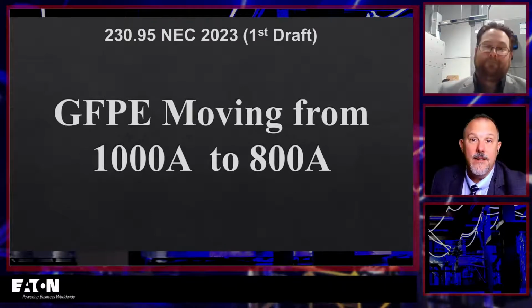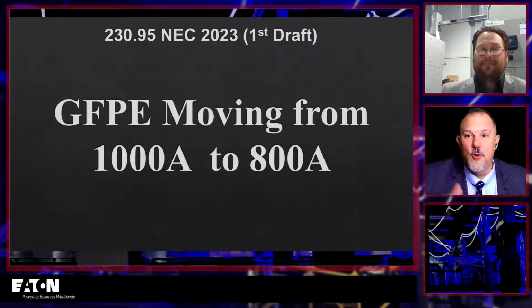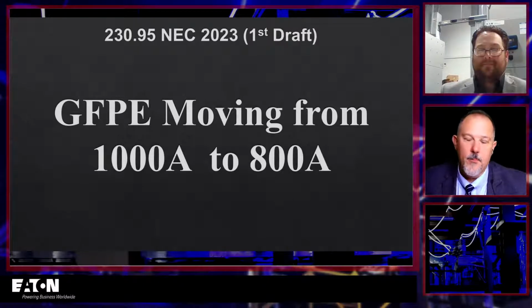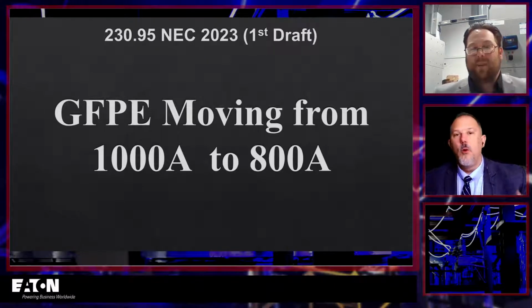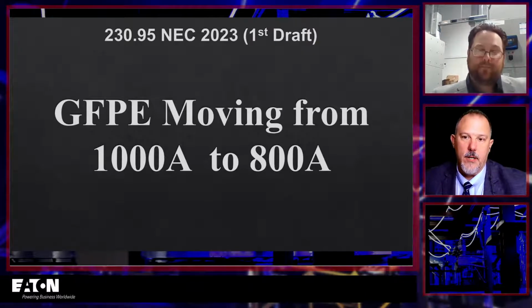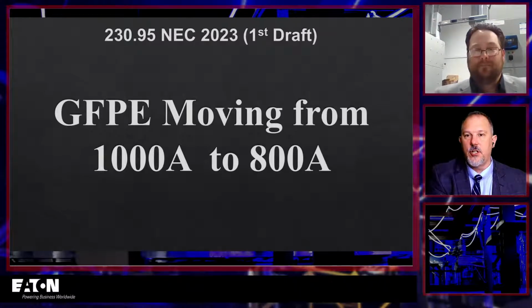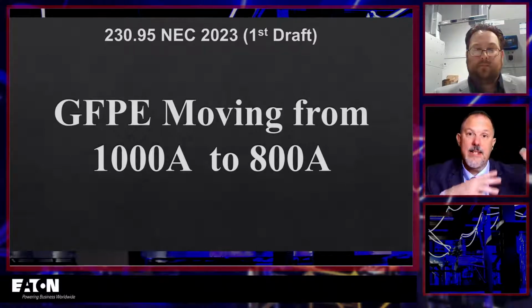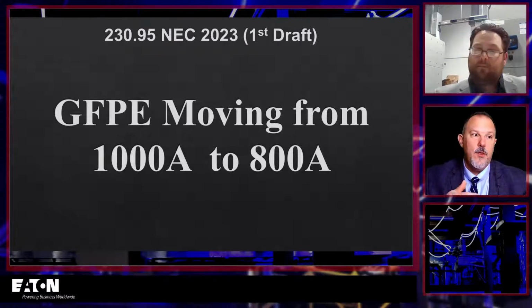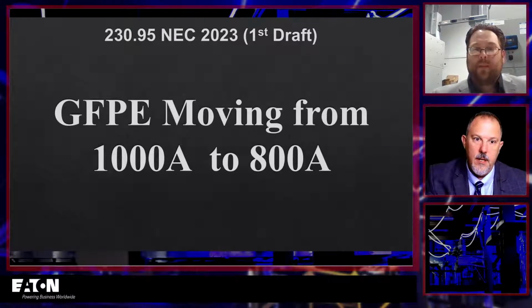Why would I have done that? I would have taken a panelboard with maybe 400 amp breakers instead of one 1200 amp or one 1600 amp breaker, because I don't have to do GFPE, right? It lowers the technology that's in my service entrance equipment. I can have up to 6 disconnects in one panelboard. Now all of a sudden, I can't do that anymore, and I have to either have a main in there, or a disconnect switch or something like that. So they're making it harder to get around these types of requirements, and they're lowering it because of issues that we're seeing in the field.